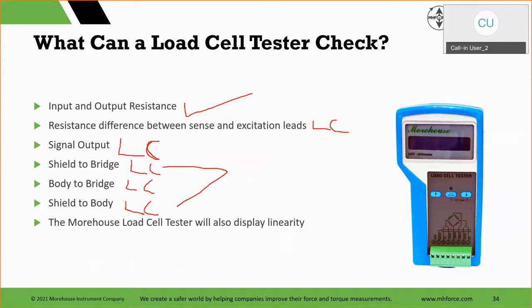These 3 things, people throw out lots of good load cells when it's just some corrosion in the line or the cable's gone bad. And the other thing that this will do is, if you wanted to know linearity, you can have this in live mode where it'll actually display linearity. You can put the full scale on it and see what it reads at 50%. So if you're wondering how linear my load cell is, that's an added bonus here. We sometimes use it. There may be value in several, but the big value here is really this for diagnostic and keeping some process control on your instrumentation, is that signal output or zero balance. The secondary outputs are like input resistance, shield to bridge, bridge to body, shield to body.